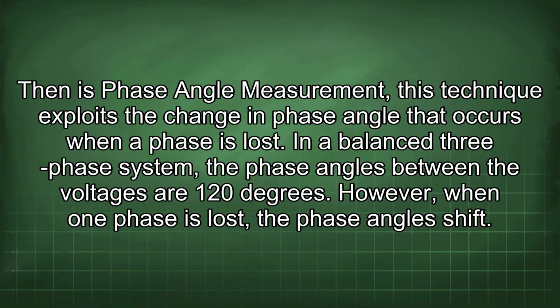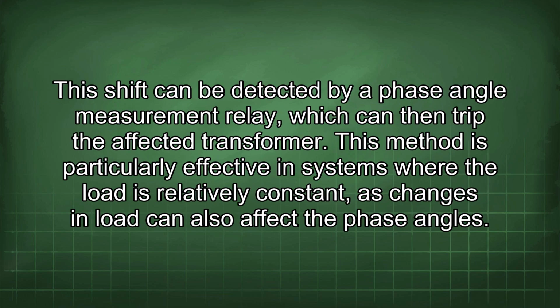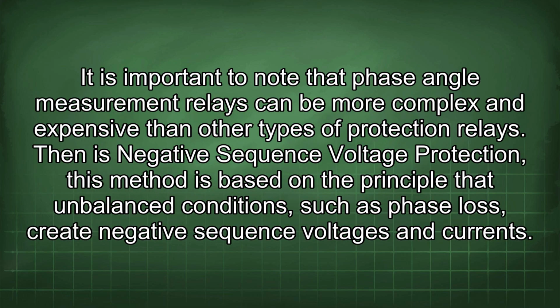Then is phase angle measurement. This technique exploits the change in phase angle that occurs when a phase is lost. In a balanced three-phase system, the phase angles between the voltages are 120 degrees. However, when one phase is lost, the phase angles shift. This shift can be detected by a phase angle measurement relay, which can then trip the affected transformer. This method is particularly effective in systems where the load is relatively constant, as changes in load can also affect the phase angles. It is important to know that phase angle measurement relays can be more complex and expensive than other types of protection relays.